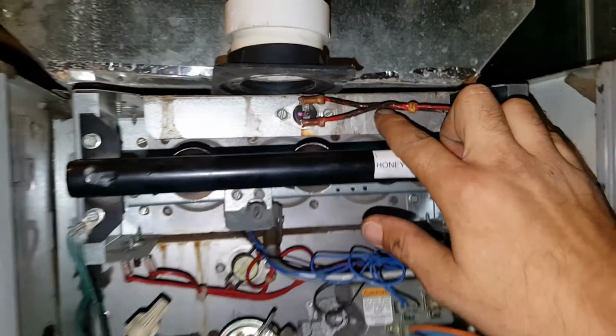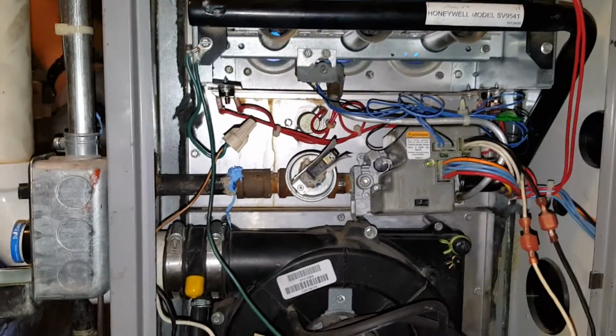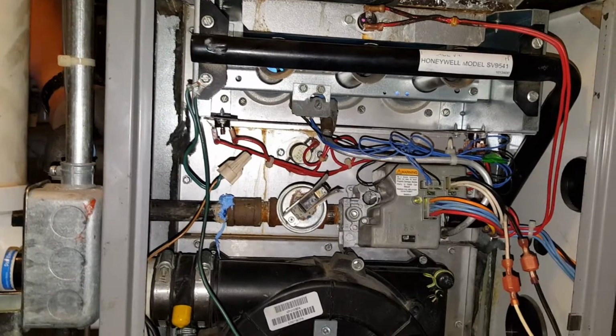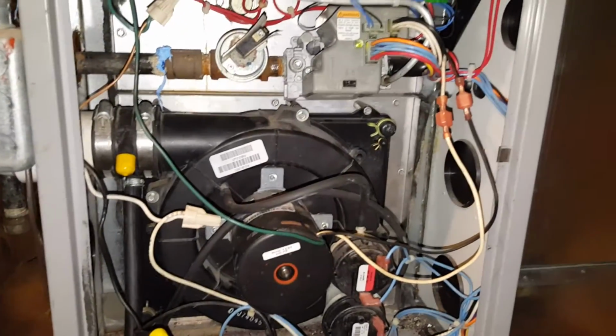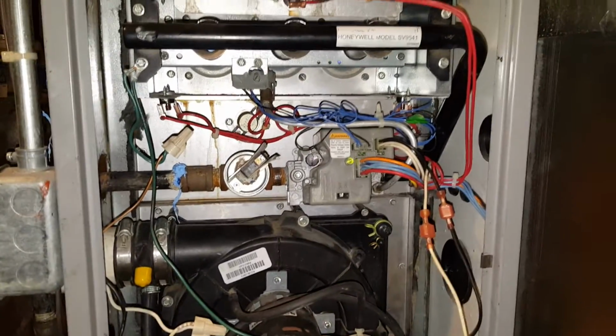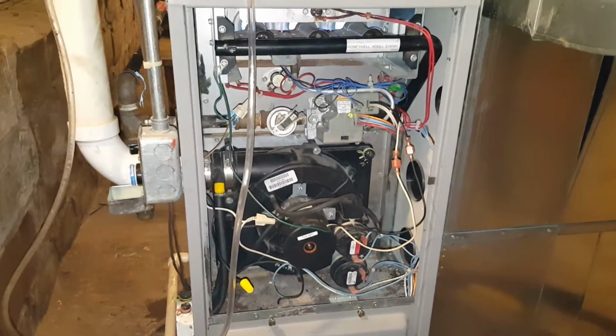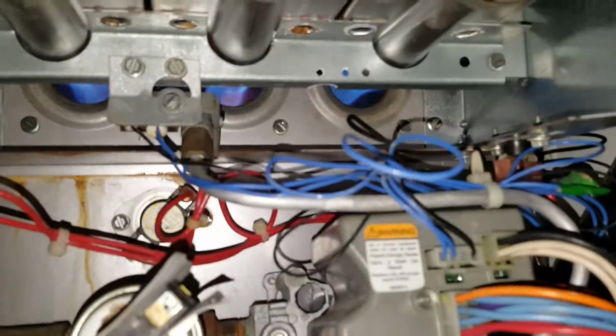But right now we need to do a carbon monoxide test, to make sure we're under 100 parts per million in the chimney leaving this unit. So we'll let this guy get up to temp, and then we'll do the big test. Okay, so we are up and running, we are firing.